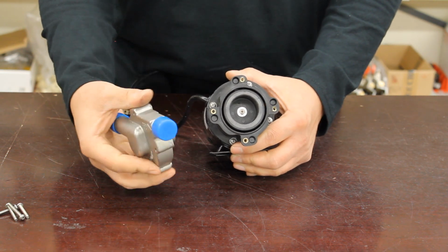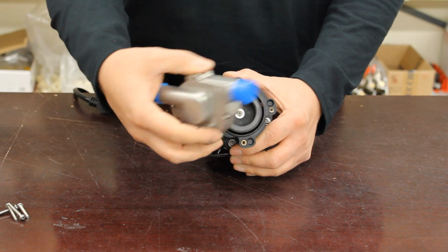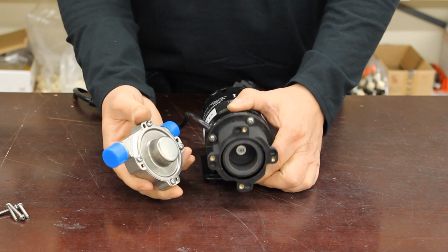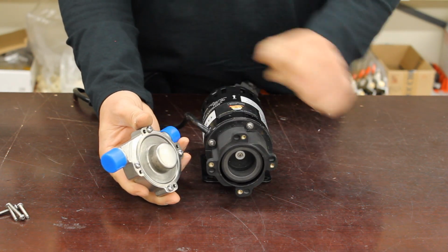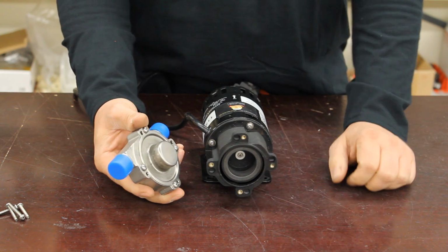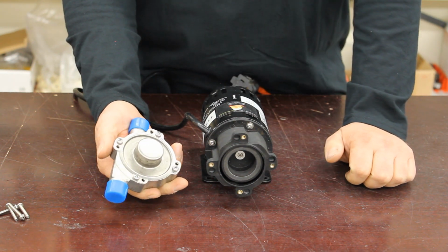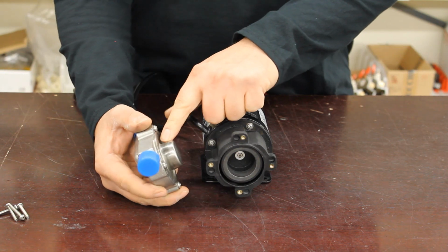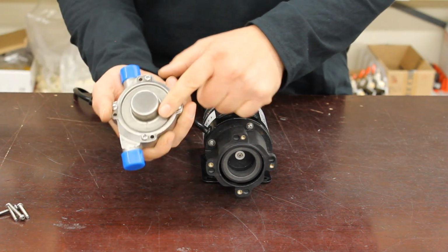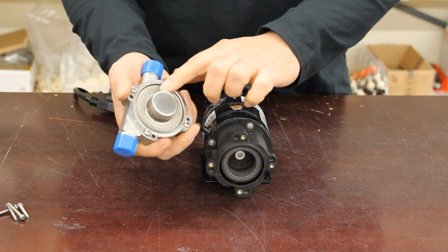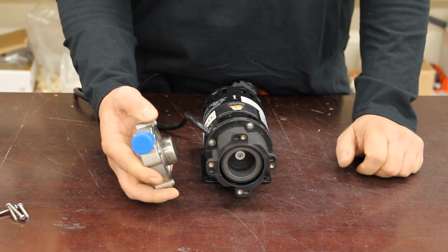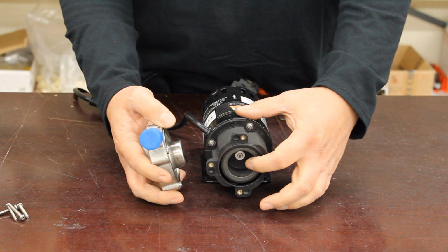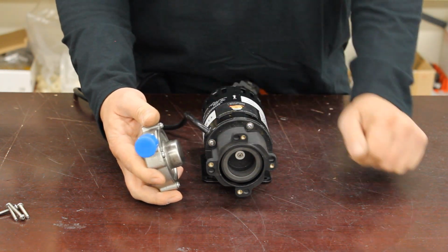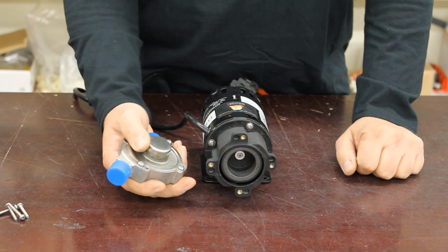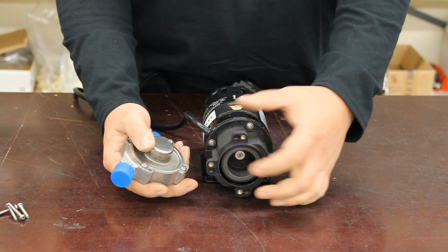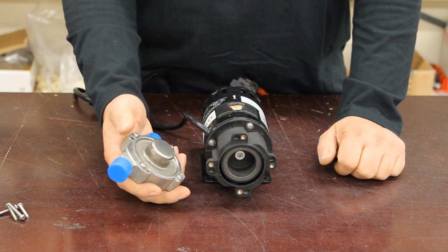And again, because these tolerances are so tight, there could be some contact made between the back cover plate of the head and the cup magnet. So this could simply be an alignment issue. And you can also verify, you might want to look on the cover plate of the head and look for abrasion marks. What it normally would look like is a shiny section where the cup magnet was kind of polishing a certain spot on here, and that would be a telltale sign that you have a contact issue between the cup magnet and the back of the head.